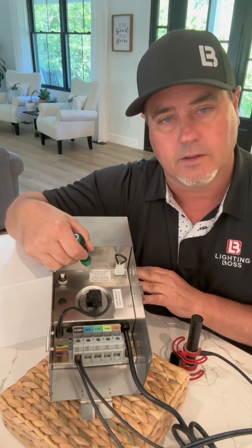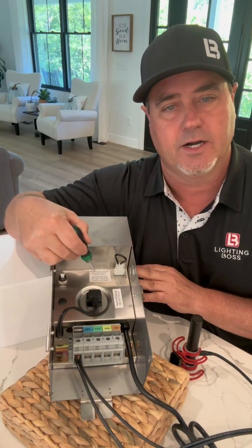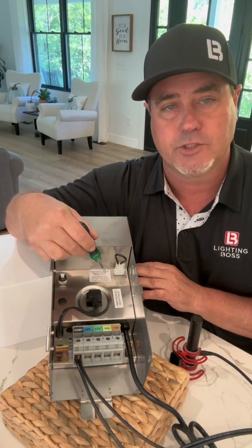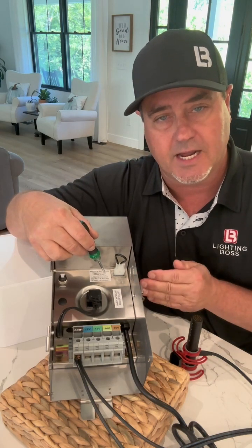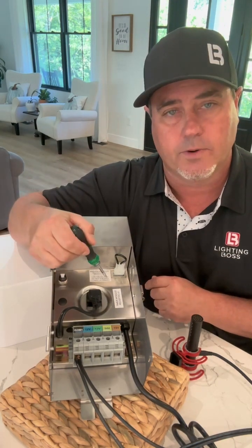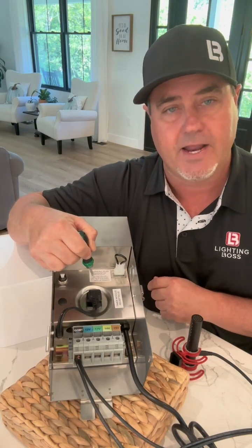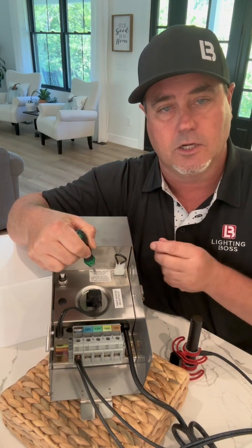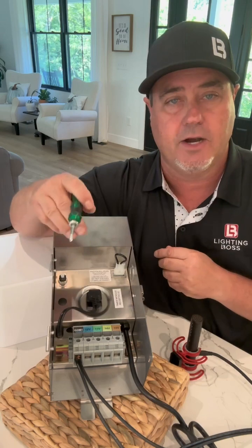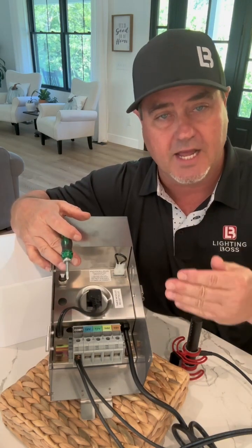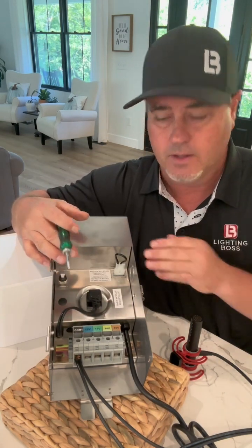Up here, a lot of the transformers are going to have a little sticker that tells you what that amperage reading needs to be on the primary side. On this particular transformer, it tells us 2.5 amps for the primary side. So once you do your reading, as long as you're at 2.5 amps or less, you should be just fine.